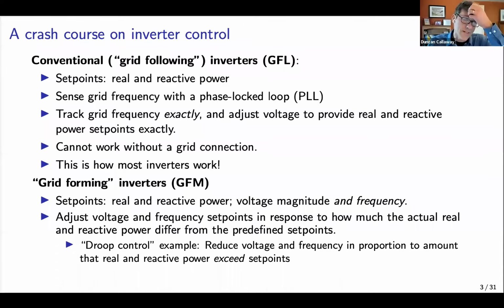So a droop control example, and this is what we'll be studying in the talk today, is one in which suppose that frequency and voltage magnitude on the grid were to go down, then the real and reactive power of the inverter would change in response. Or actually, the better way to say it would be, suppose that that power electronic converter is attempting to maintain some set points. As a consequence, real and reactive power change. When it senses that, the grid forming converter will then reduce its frequency and voltage in response. And so in that way, it's setting its own voltage magnitude and its own frequency. What's remarkable is that these devices can synchronize themselves. And so you can operate them essentially in parallel. And there's been a lot of really important work with regard to grid forming inverters around that question of synchronization.